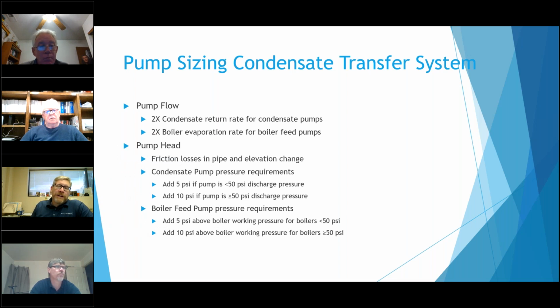The pump head, again, it's fairly similar. It just really depends. It's very similar as far as you figure it up. So you got pipe lengths and everything like that. Once you get this, you do have to worry about elevation changes. Like for condensate pumps, a lot of times that's going into a deaerator. So you got to overcome whatever the deaerator pressure is.